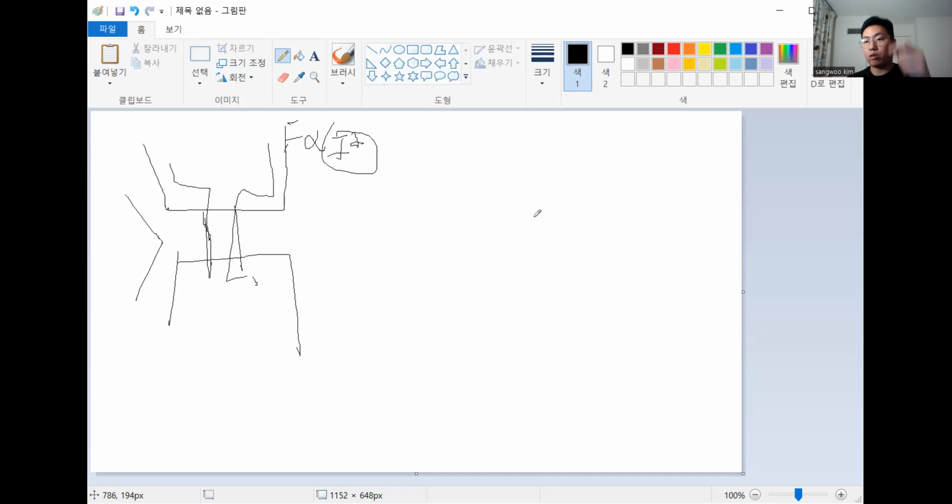So which means the contactors are going to be totally welded, so they cannot open. Even though the breaker needs to open the circuit, because of the bounce and the arc, they are welded. So the result is the circuit breaker fails.